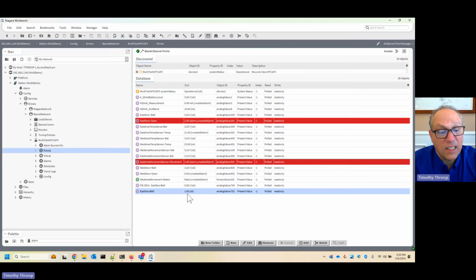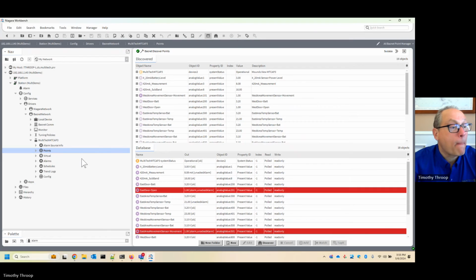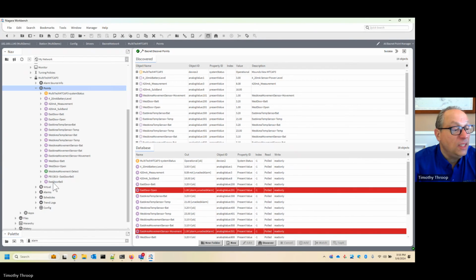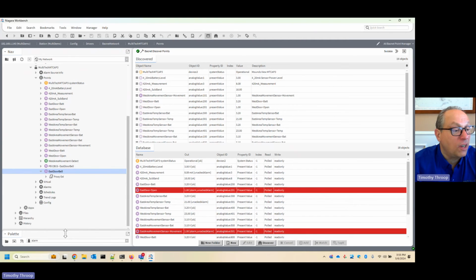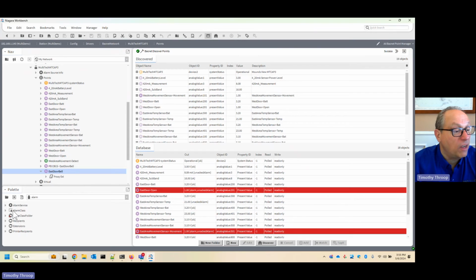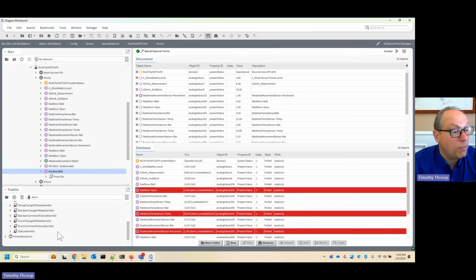The whole point here is that I can send an alarm or some kind of message or indicator that this particular event has taken place. Let's do that — let's go to our points, East doorbell. I'm going to create an alarm for this. This goes a little bit beyond what we normally would do here, but it shows how powerful this is, and how we're part of this whole ecosystem of BACnet objects, sensors, and valuable data.